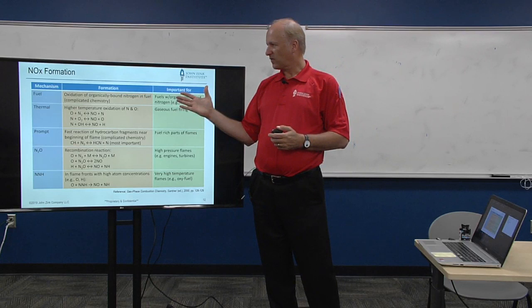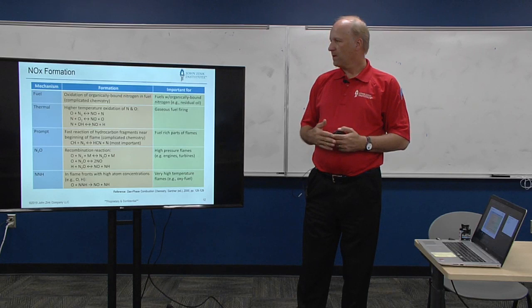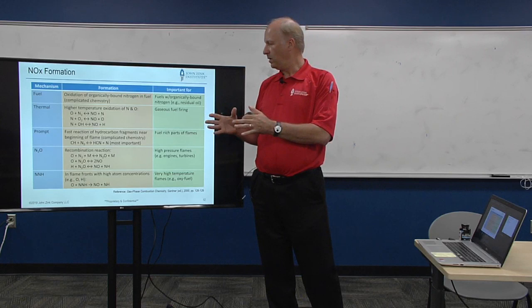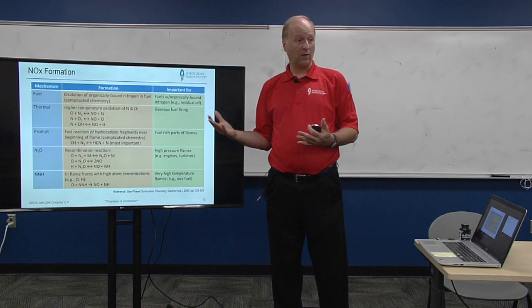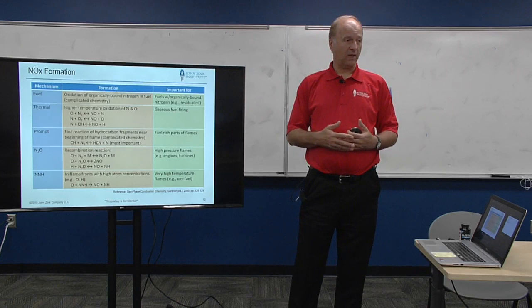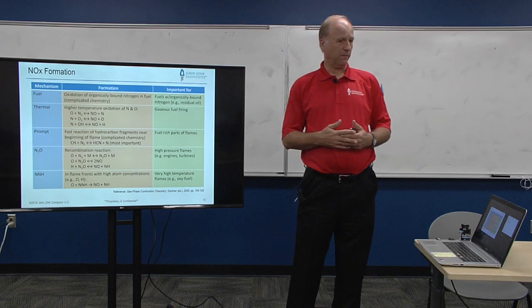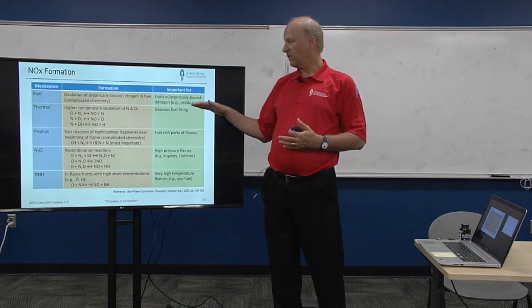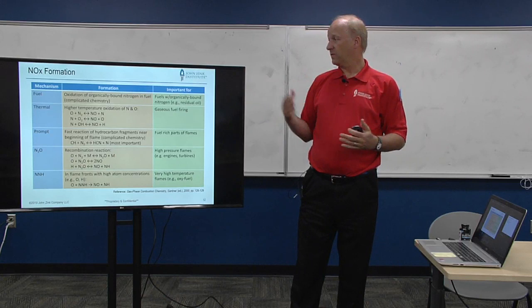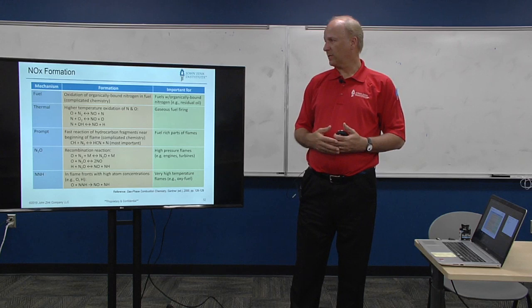Here's a table summarizing how NOx forms by various mechanisms. Fuel NOx is where you have organically bound nitrogen as part of the fuel — an example might be ammonia, NH3. The N comes off very easily, unlike N2, which is a very stable molecule with a triple bond. Ammonia is a fairly common component in fuel systems, sometimes added downstream through other processes. Thermal NOx is the one we'll spend most time on today — it's a temperature-driven effect, which is why it's called Thermal NOx. It was discovered by a Russian scientist named Zeldovich in the 1950s, so you'll sometimes hear it called the Zeldovich mechanism, specifically the extended Zeldovich mechanism.